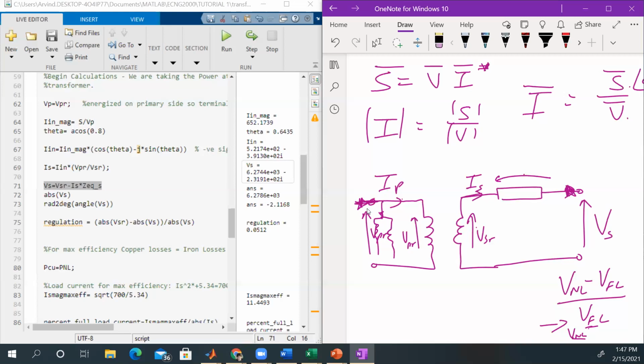I think there was actually a past paper question with that, where we took it on the secondary side, and when you calculated the voltages on the primary side, it was actually more than the rated voltage. And then the question was, well, what is wrong here? So anyway, that is just to tell you that with things like regulations and so on, there's no absolute right or wrong. When you look at whether it is full load or no load, a lot of them just give you some information about the transformer, and whichever one you adopt, you just have to make these little adjustments to the values that you'd get, in telling you how good the transformer is.